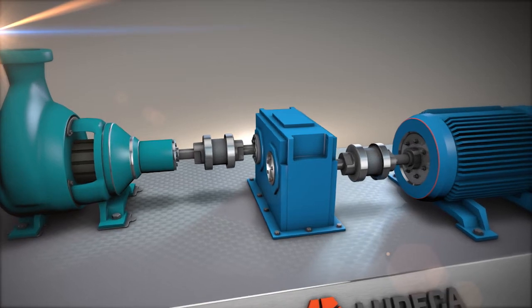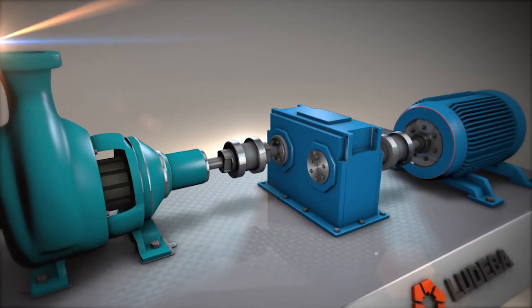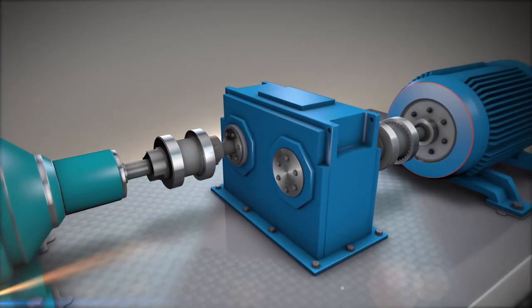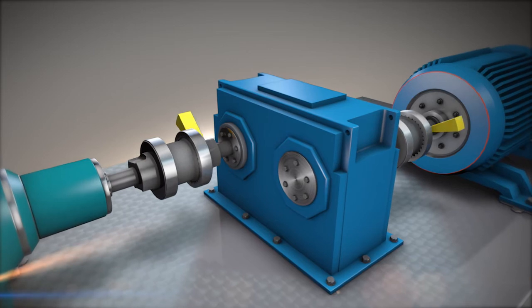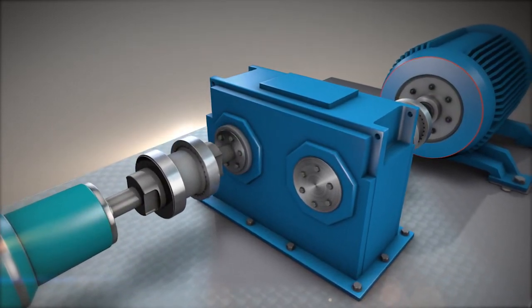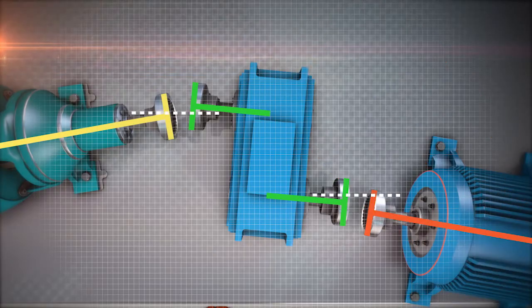When faced with this situation, the goal is to find the best solution to prevent a bolt-bound or base-bound problem. For that, we measure the alignment across each coupling to obtain a clear idea of how each machine is aligned with respect to the other. We remeasure for repeatability.